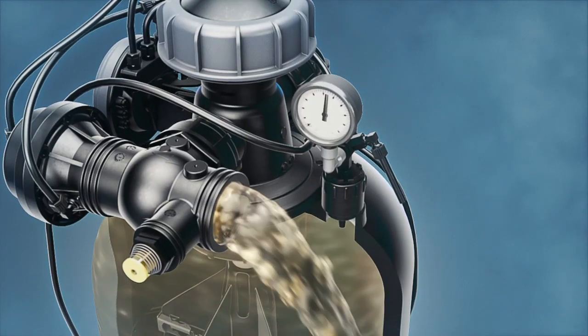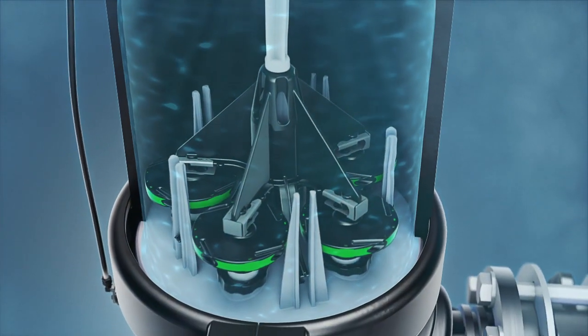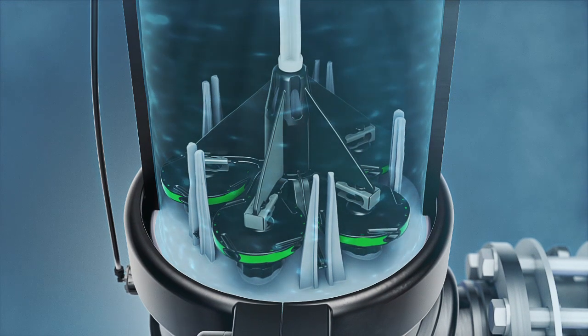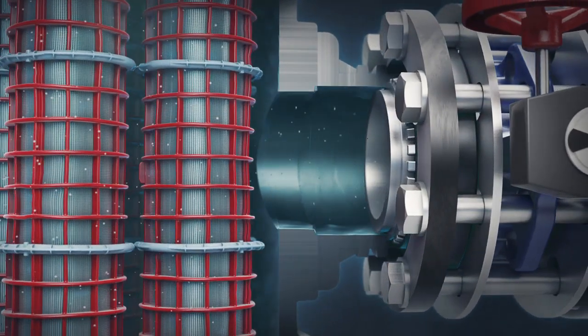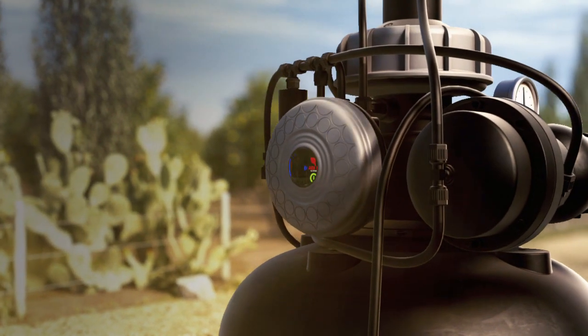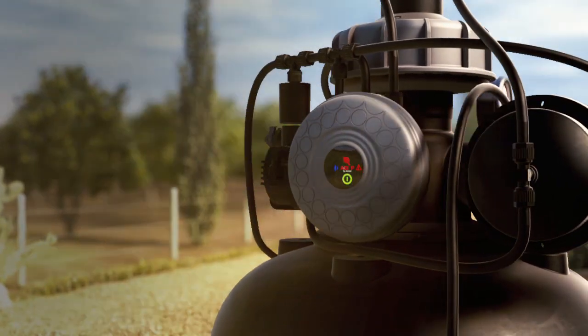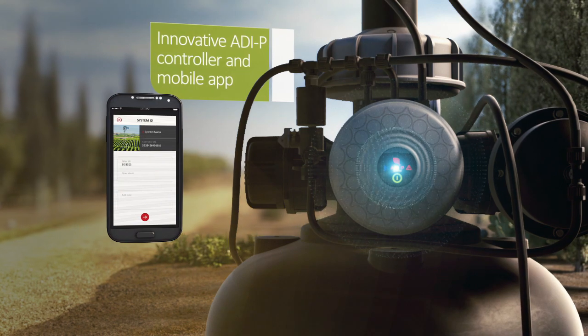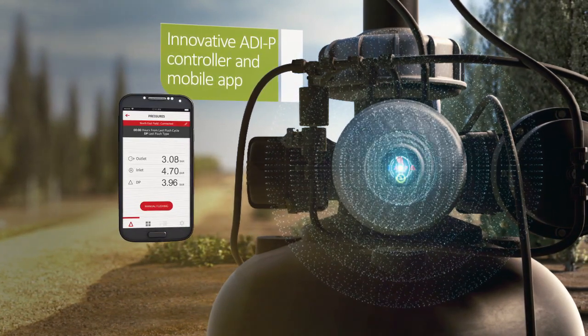Once the filter cake is removed, the pressure differential returns to normal, the filter resumes its standard filtering mode, and is ready for the next flushing cycle. Throughout the cleaning cycle, water continues to flow through the filter's outlet. Sigma Pro also offers the ADI-P controller, developed by AMIAD for its filters, which interacts with AMIAD's mobile app for one-of-a-kind monitoring and control.